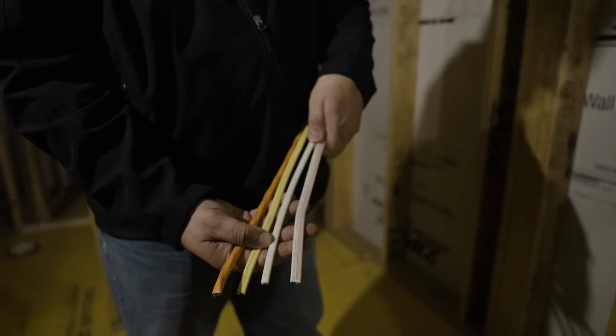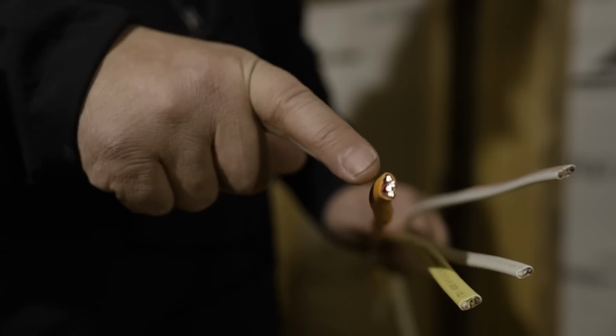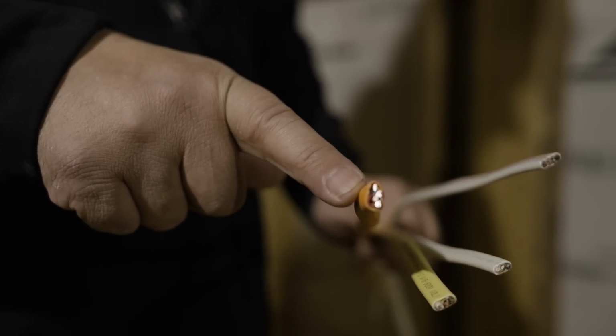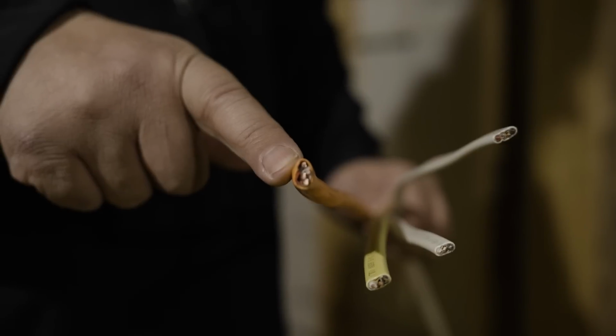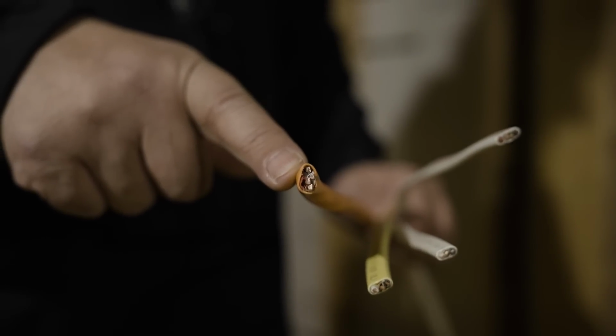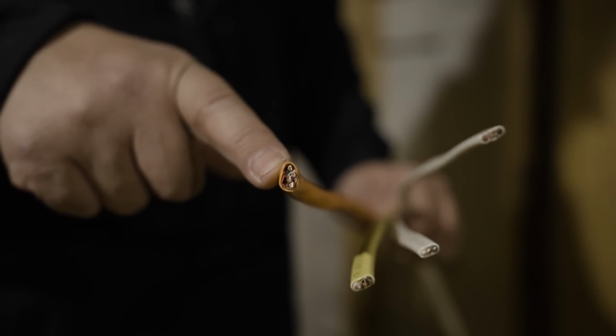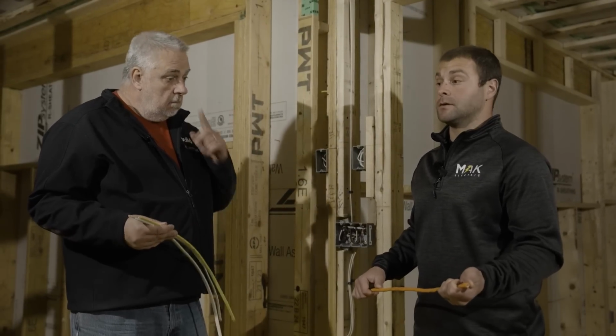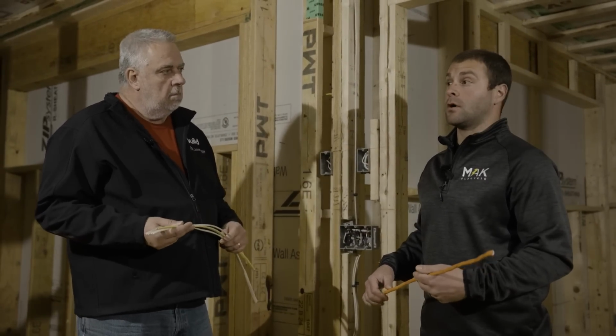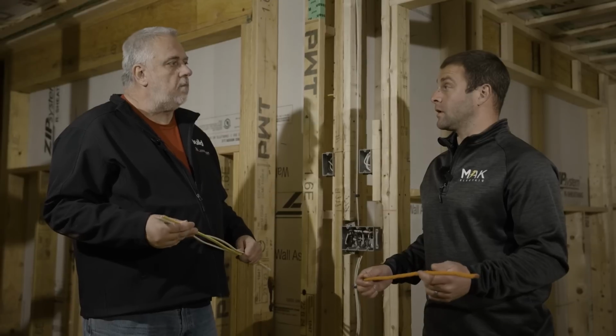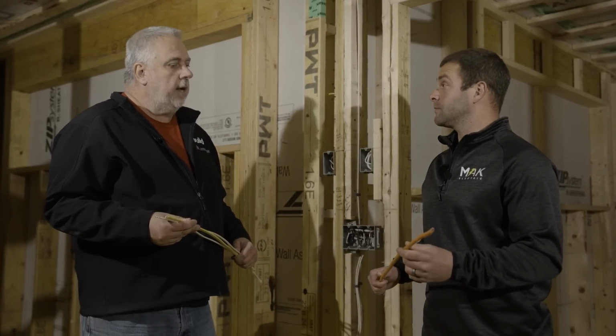Let's start with one we probably don't use a lot, but it's important, right? The big heavy one. Yep, this is a 10 gauge wire, good for 30 amps in a house, and typically we're going to use it for dryers, some AC condensers, a lot of things that draw more amperage. We're going to use number 10 for it, and it's good up to 30 amps.